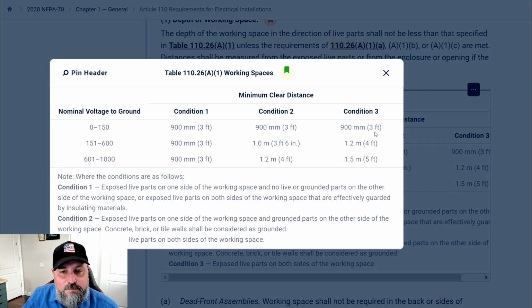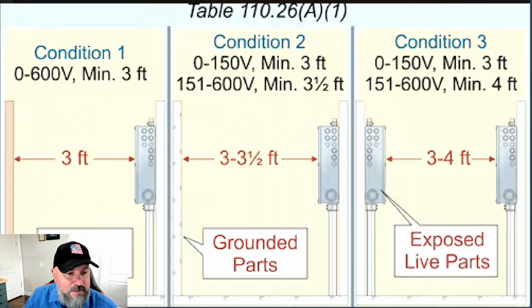So panels facing each other, 4 feet, if it's 480/277. Condition 1, 3 feet. Grounded, 3 feet 6 inches. You have to add that if it's grounded, and then 3 feet. So let's go into some pictures about that. So this may better explain it. Let me just find that here.